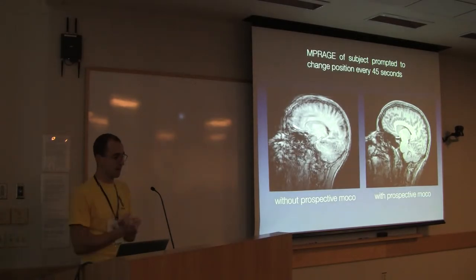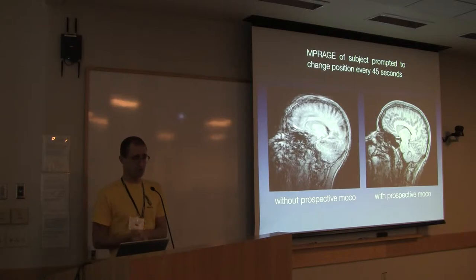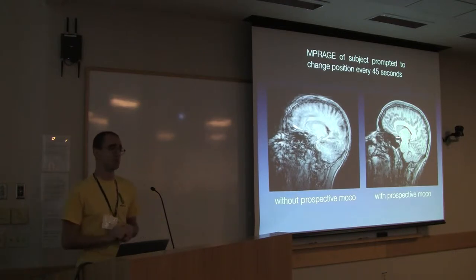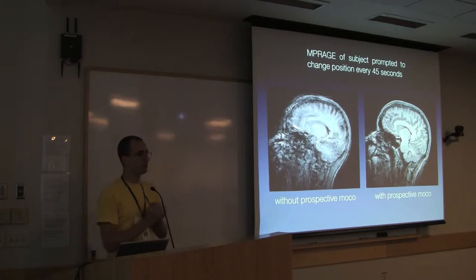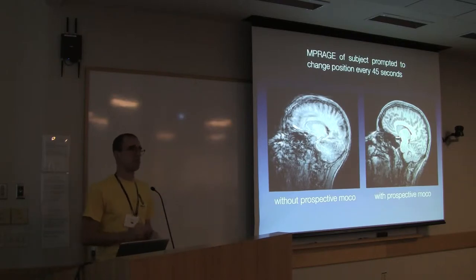This is an MP-RAGE of a healthy normal subject who was asked to change position every 45 seconds during a six-ish minute scan. This subject did not thrash around in there. These were relatively small motions - rotations of less than eight degrees, translations smaller than 20 millimeters, two centimeters of motion. If you just acquired the standard MP-RAGE you would get the image on the left. Obviously that is not the image you want. Using our prospective motion correction system, tracking the same subject, we get the image on the right. These were two separate scans but the subject was asked to repeat the same motions. This is a relatively obvious example of why prospective motion correction techniques are important.